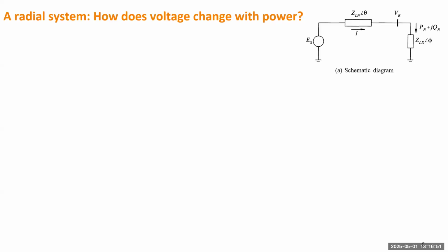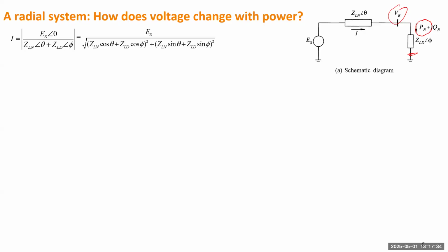Let's use this simple system to understand how voltage instability can happen. Basically, we want to figure out how the voltage at the load bus changes. This load bus is just connected to a constant impedance load. This impedance can change. When the impedance decreases, the load will increase under normal conditions. So we study how the voltage magnitude changes with the active power. First, we can calculate the current. This is the absolute current, the magnitude of the current, which is equal to the voltage of the source divided by the total impedance. Then we take the absolute value.